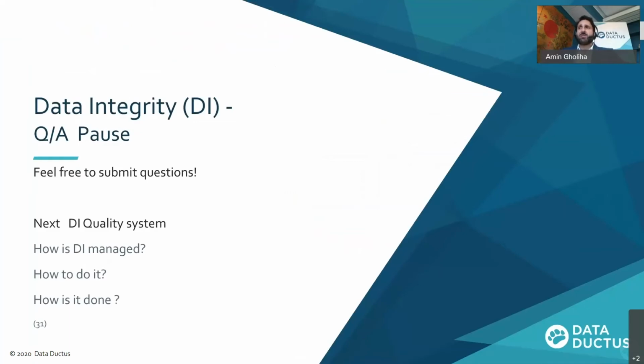Okay. Now we have covered audit trail, what it should do, and the difficulties with it. Audit trail is very important, and usually when customers put requirements on audit trail, they put a few requirements, 1 or 2 or 3 or 4, or sometimes they just take the Part 11 requirements straight ahead and put them in their requirement list. But in practice, you need to have 20, 30, 40 plus different requirements just related to audit trail. So it is very important to do it right and make sure that you have the right tool at your disposal when you purchase or develop customized systems.